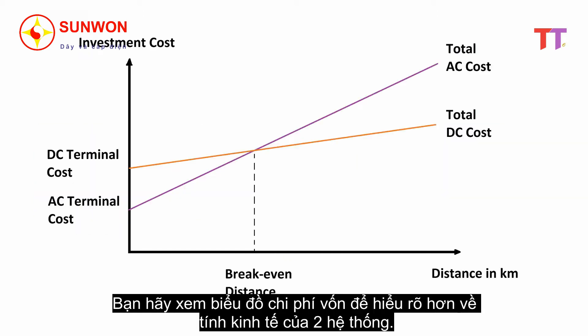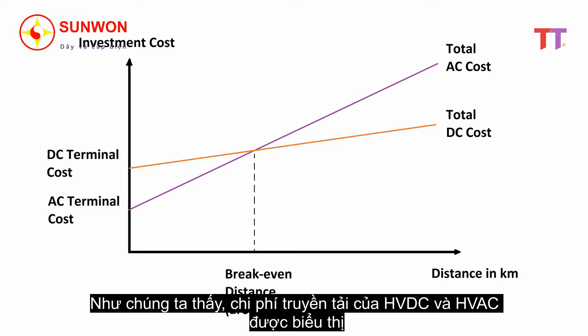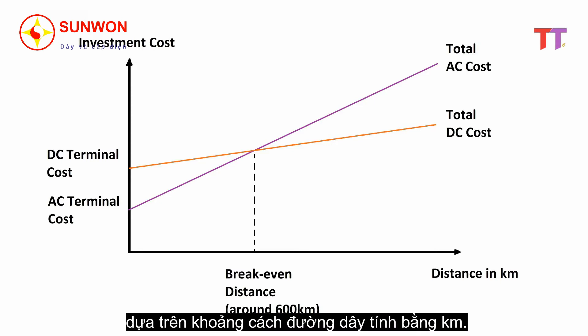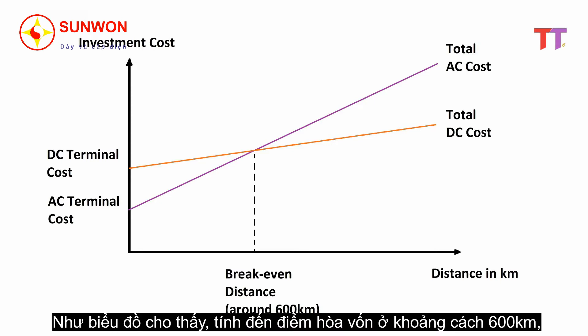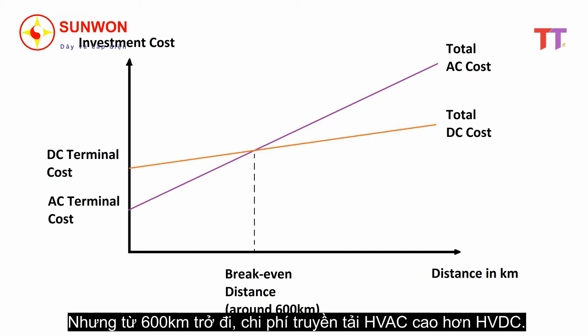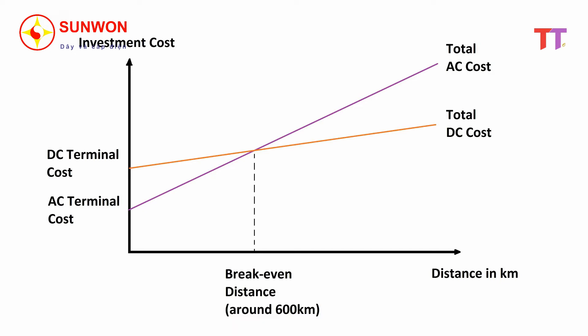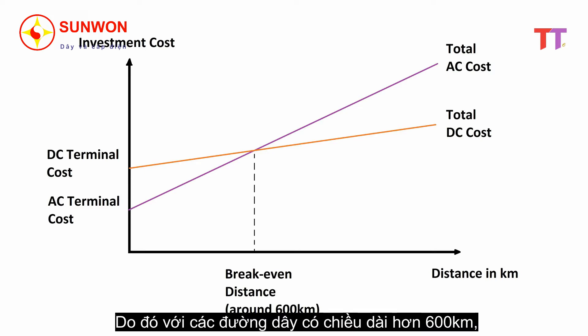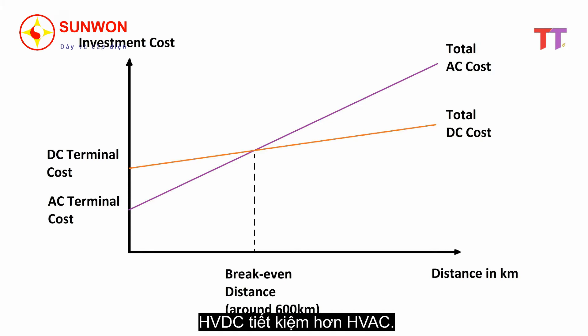Considering the capital cost, and for better understanding of the economics of both systems, let's see the graph. As we can see in the graph, HVAC transmission cost and HVDC transmission cost is plotted against distance of transmission lines in kilometers. As shown in the graph, up to the break-even point — that is around 600 kilometers — cost of HVDC transmission is higher than that of HVAC transmission. Whereas after 600 kilometers, cost of HVAC transmission is higher than that of HVDC transmission. Hence for transmission beyond 600 kilometers, HVDC transmission system is economical as compared to HVAC transmission system.